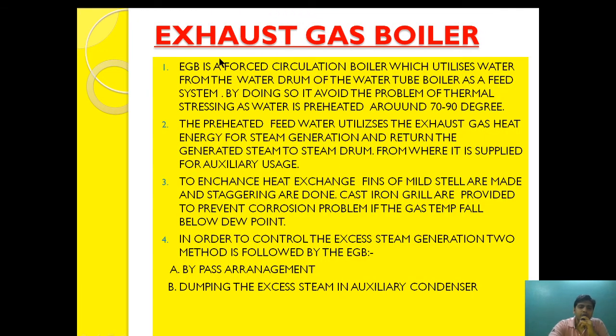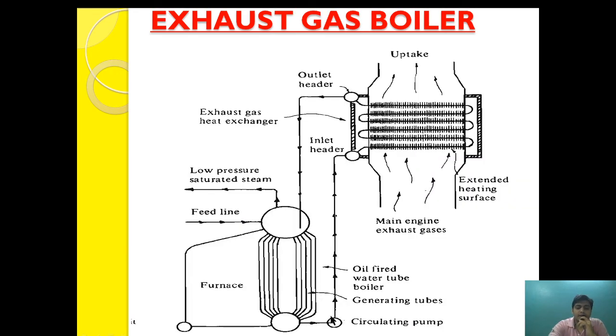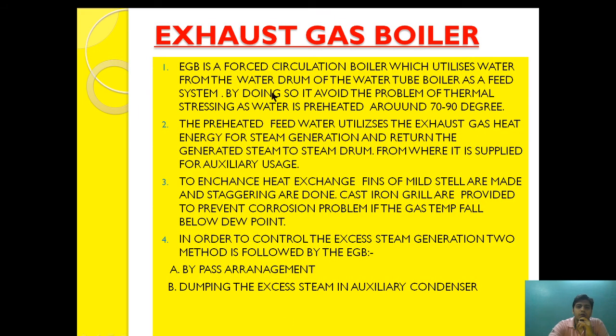The exhaust gas boiler is a forced circulation boiler which utilizes water from the water drum of the water tube boiler. It is forced circulation because the water is pumped to the inlet header — it does not flow naturally. Water is taken from the water drum and pumped to the inlet header, where it absorbs heat from the engine exhaust gas and is converted into steam.